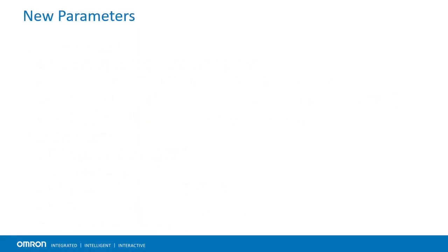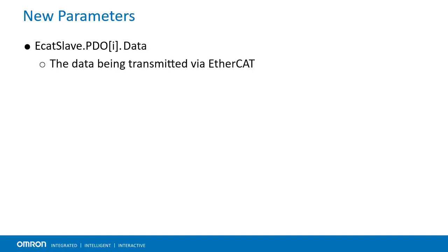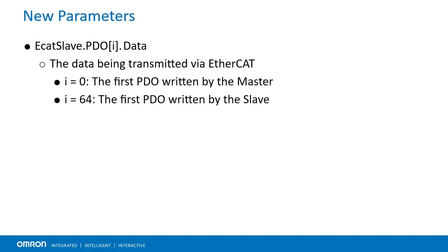Next, we will discuss parameters using the ECATSlave.PDOindex[i] prefix. Most importantly, ECATSlave.PDOindex[i].data contains the data being received and transmitted over EtherCAT between PMAC and the master device. Indices 0 through 63 contain data being written by the master to the slave, while indices 64 through 127 contain data being written by the slave to the master. Users will not be able to write to indices 0 through 63 while EtherCAT is enabled.